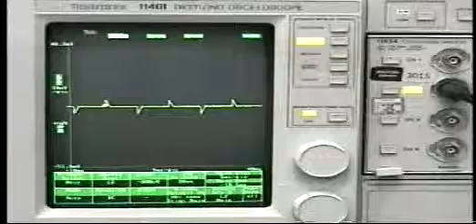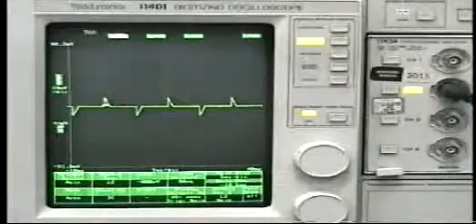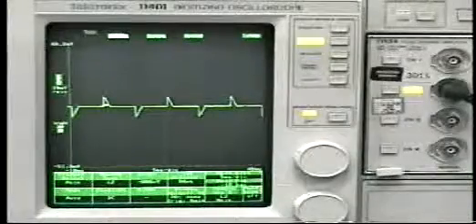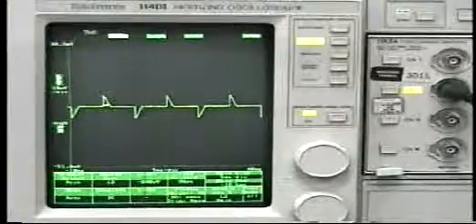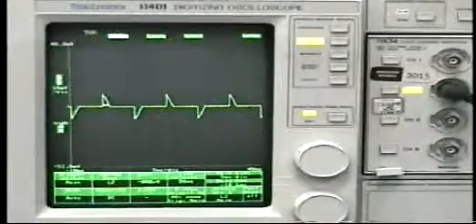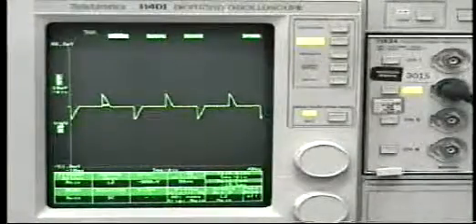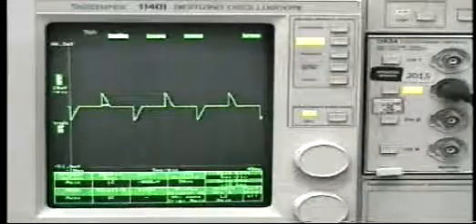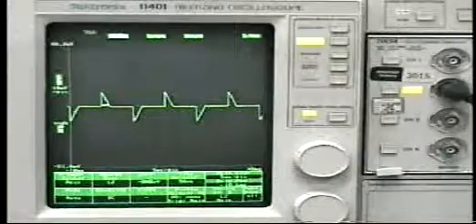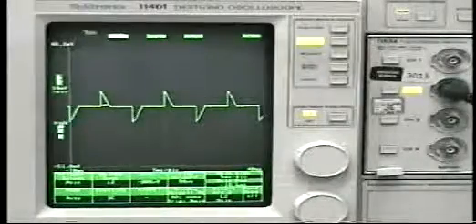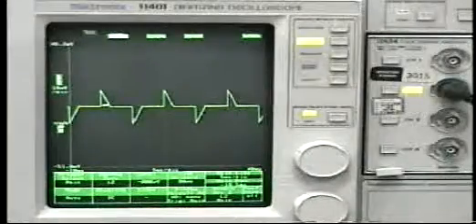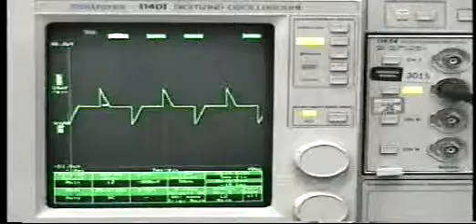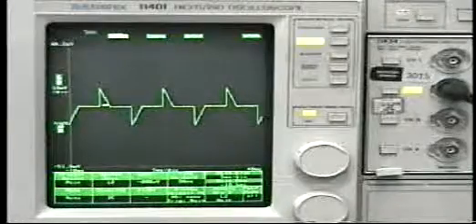The power series uses phase angle firing to increase the voltage applied to the load at a rate defined by the bakeout time. The load current is compared to the overcurrent trip value as the voltage is increased.